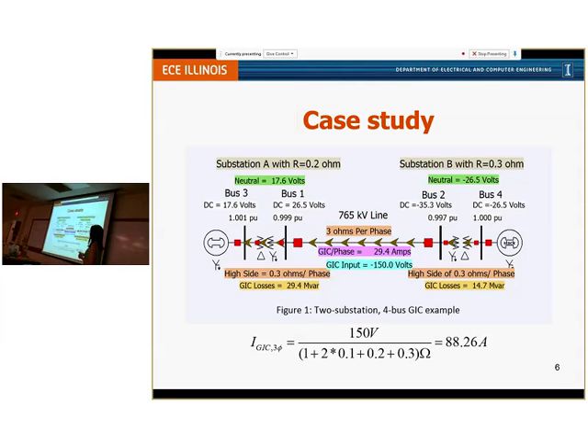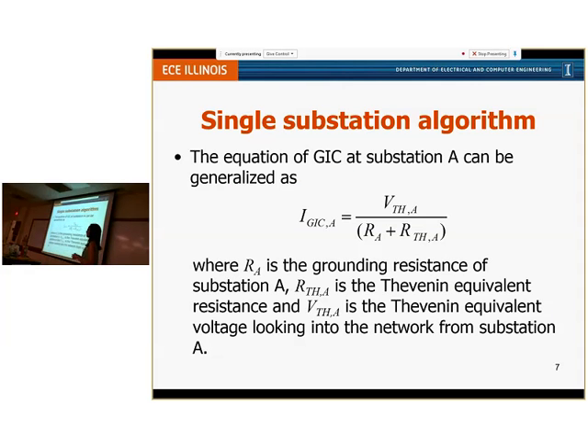Below we have the equation for the three-phase GIC at substation A and also B. Using the calculation, we got the result of 88.26 amperes, which means the GIC for one phase is about 29.4 amperes, and that value agreed with the result of our simulation using the power simulation software. Then we can generalize the equation in the previous slide to get the equation of GIC at substation A according to RA, RTHA, and VTHA. RA is the grounding resistance of substation A.